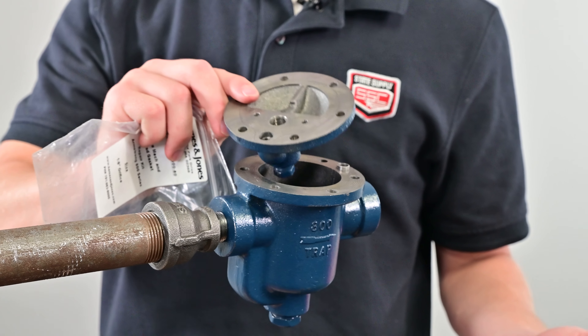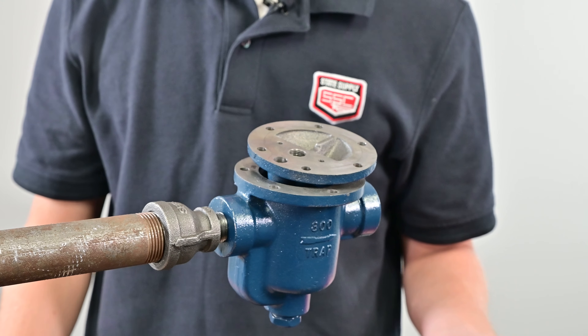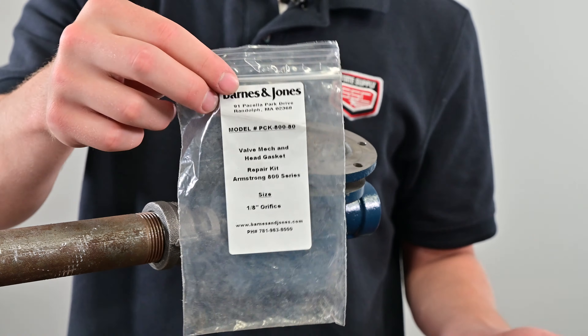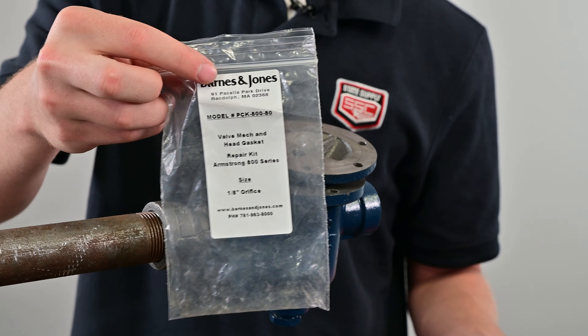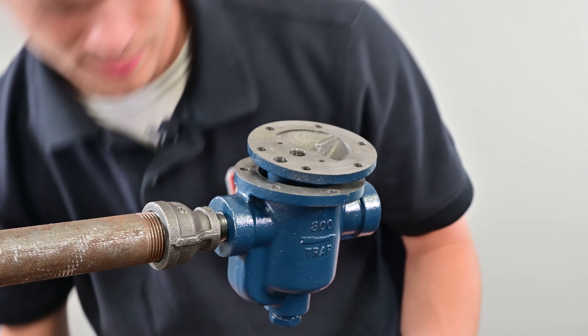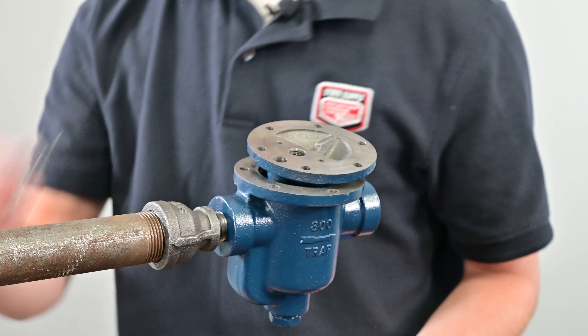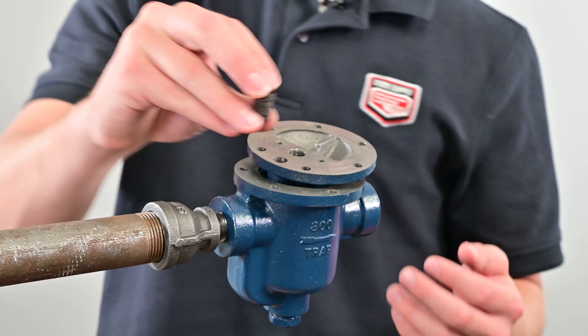Now that we have cleaned the surfaces of the trap so there's no remnants of the gasket or anything else, we can take our repair kit. In this case it's a Barnes and Jones PCK kit for an Armstrong 800 trap. Inside will be a brand new gasket, a new valve lever, a new guide pin assembly with screws, and a brand new valve seat.